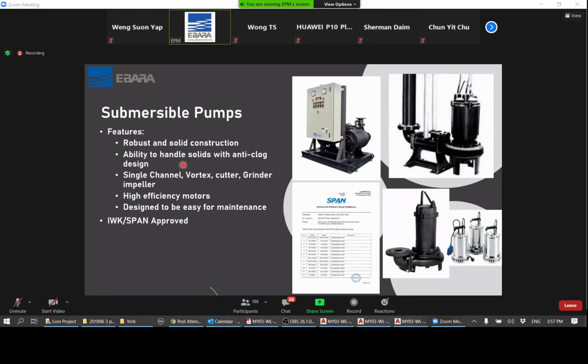One of the important features is that these pumps need to be suitable for sewage purposes, so you can put in a requirement that they be either IWK or SPAN approved. All our Ebara submersible pumps are SPAN approved, and IWK approved for those above 76 millimeter solid particle, by the end of this month.